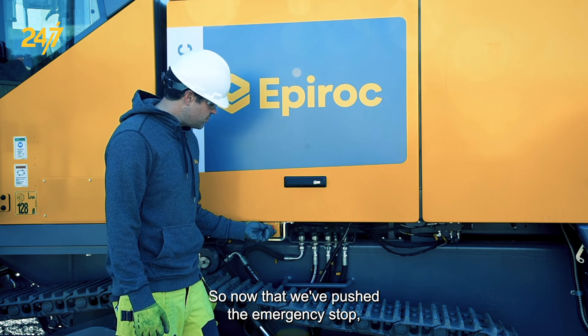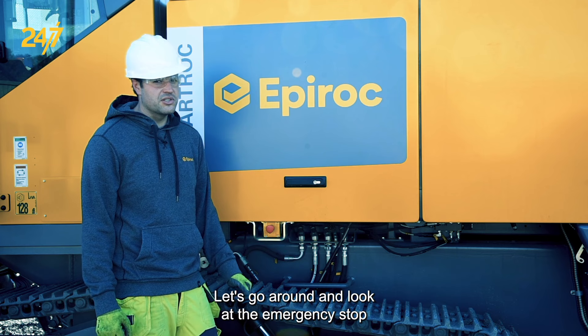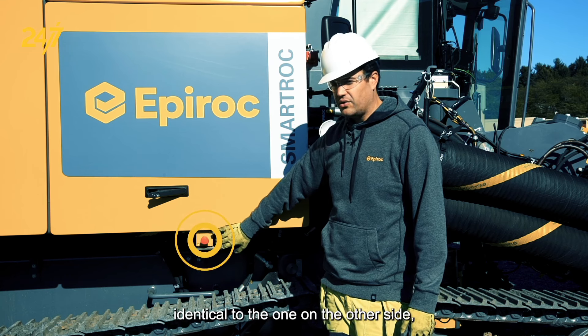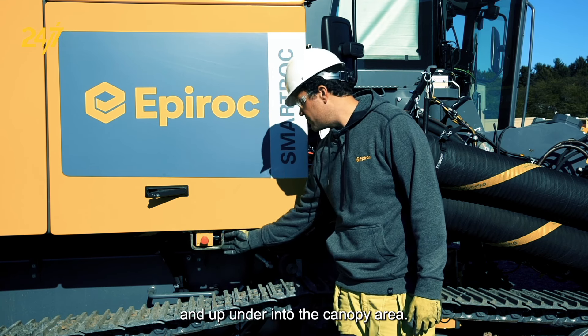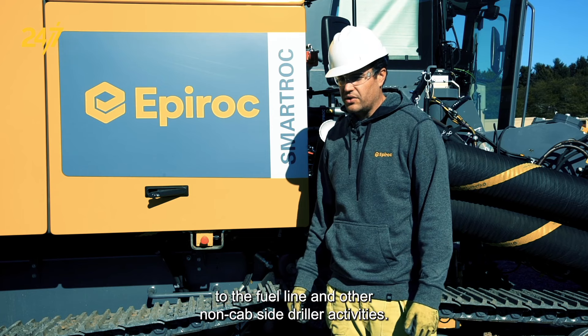So now that we've pushed the emergency stop, we twist to reset and make sure that it pops out in a positive way. Let's go around and look at the emergency stop on the non-cab side. On this side of the machine, we have another emergency stop button identical to the one on the other side, also with wires coming out of the back and up under into the canopy area. This emergency stop is placed with proximity to the fuel line and other non-cab side driller activities.